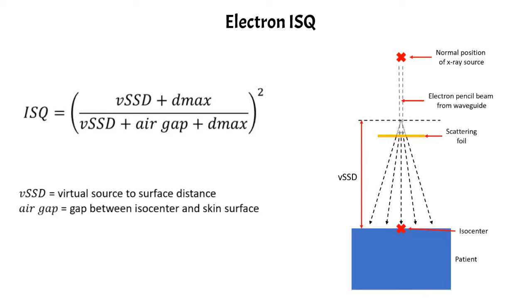And so the pencil beam starts to diverge from the scattering foil. And if we back project that beam divergence, you can actually see that the electrons appear to emanate from a point source that is located a little bit closer to the patient relative to the X-ray source. And the distance from that virtual point to the surface of your patient is your virtual SSD.